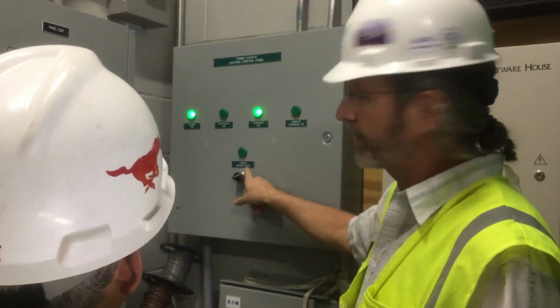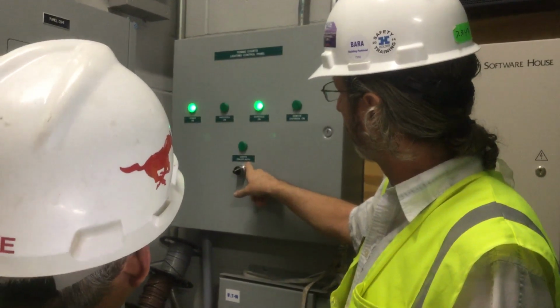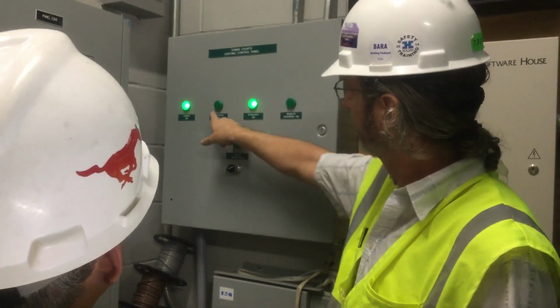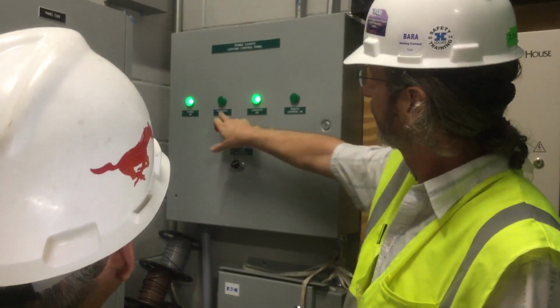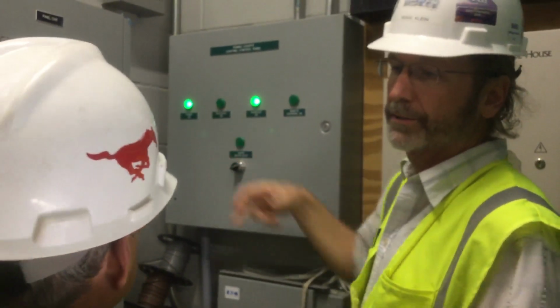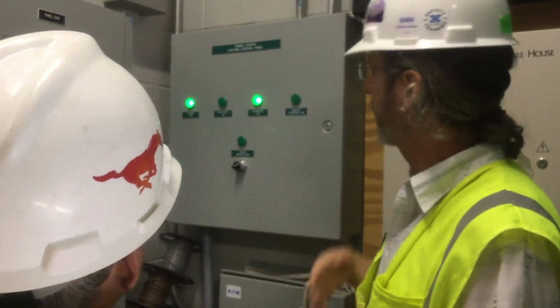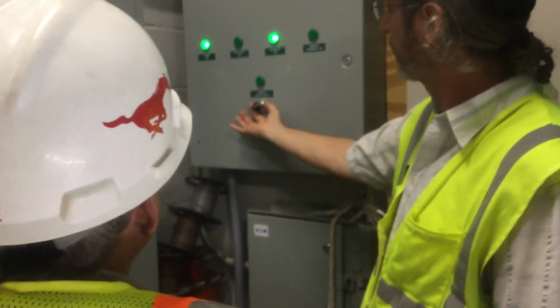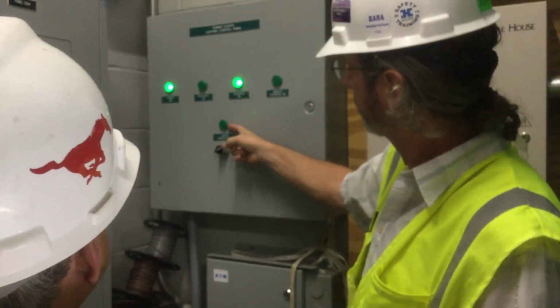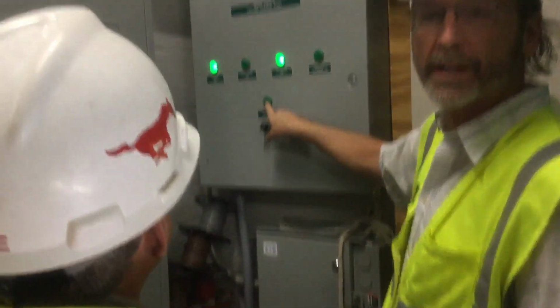In the right-hand position, auto, it will follow this - as long as the schedule is true and the photocell has gone dark, the push button will start it, and it will time out and shut off. That's in auto position. When I'm in the center position, off, it shuts off - it's done. By the way, this is a status light of the status of the lighting contactors.